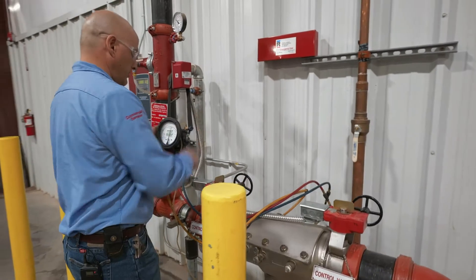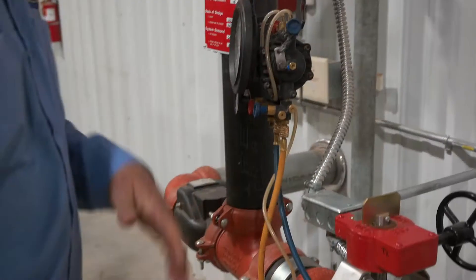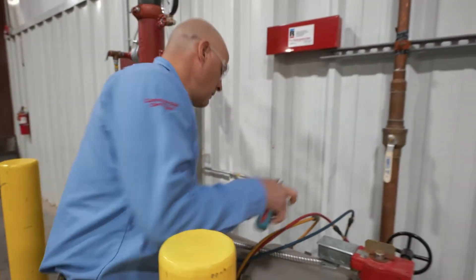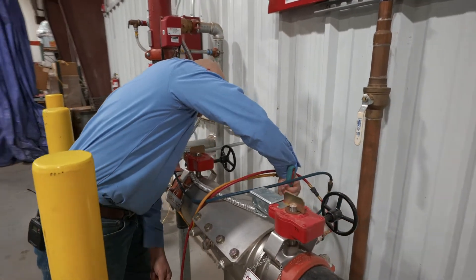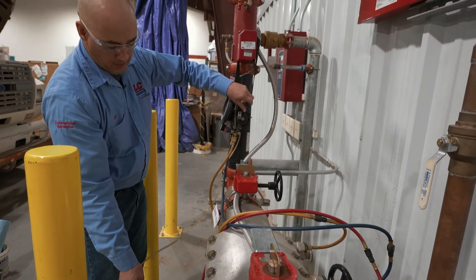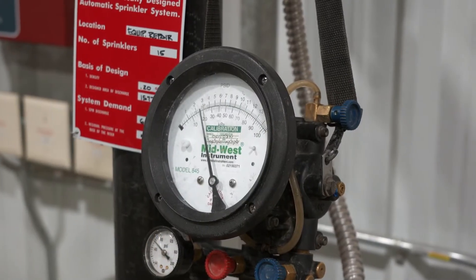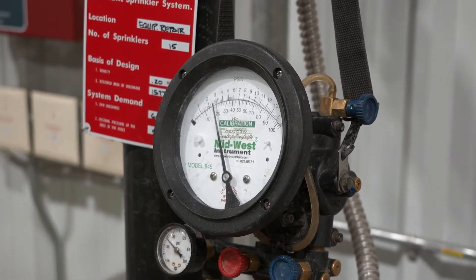Got to switch our hoses. Now we're testing for the value of check valve two, which it has to hold at a minimum of one pound pressure. And it's holding at 2.8.